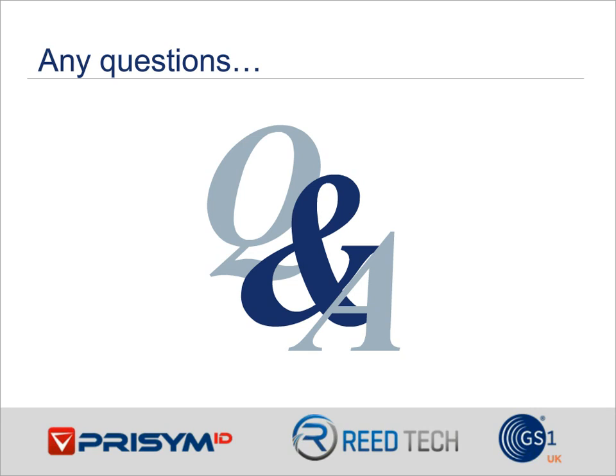And it is, when will Class 2 device manufacturers be able to open a GUDID account and submit data? Oh, actually, I had just received an update on that. It was expected to be January 1 of this year, but the FDA has delayed that to February 1. So there's actually an FDA webinar today, and I expect that question to come up there and probably be reinforced. But it's our understanding that February 1 is the date on which Class 2 manufacturers are able to get an FDA GUDID account.